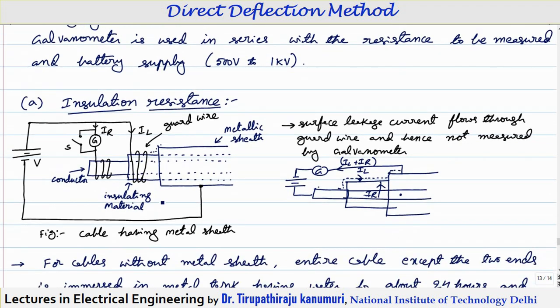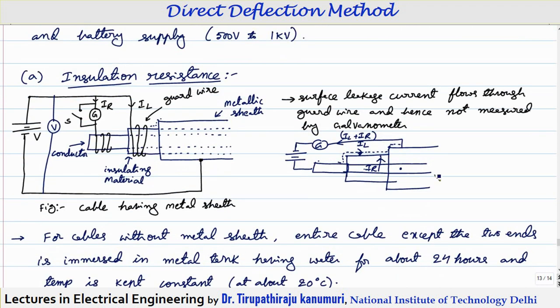If your cable has a metallic sheath, this is a simple procedure. The metallic sheath acts as the negative terminal, one guard ring is provided, and your conductor acts as the positive terminal. The current passing through the positive conductor terminal is measured by the galvanometer, and one voltmeter measures the voltage. The insulation resistance is equal to the voltage measured by the voltmeter divided by the current passing through the galvanometer — that directly gives the insulation resistance R = V/I.